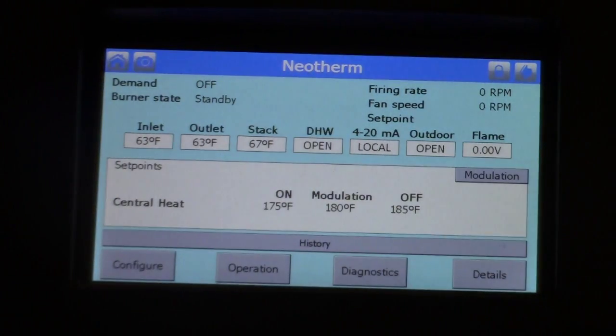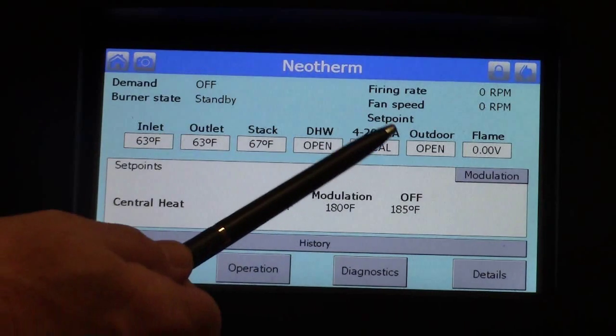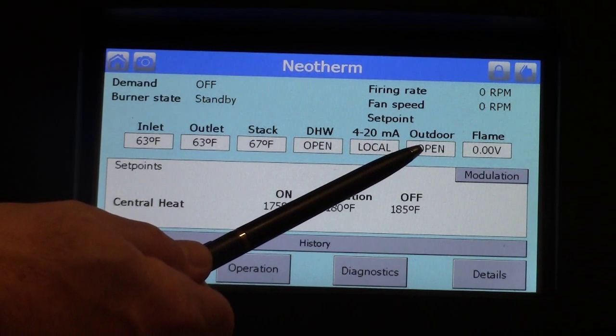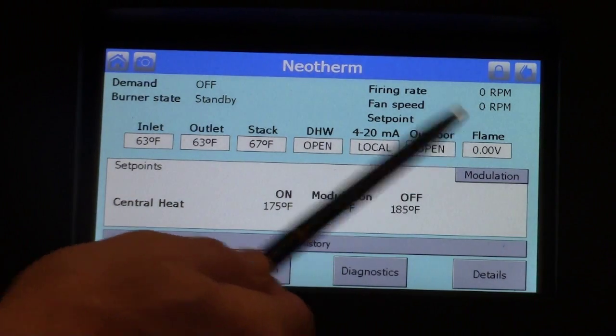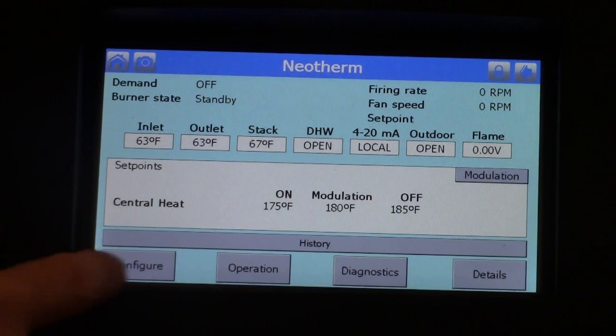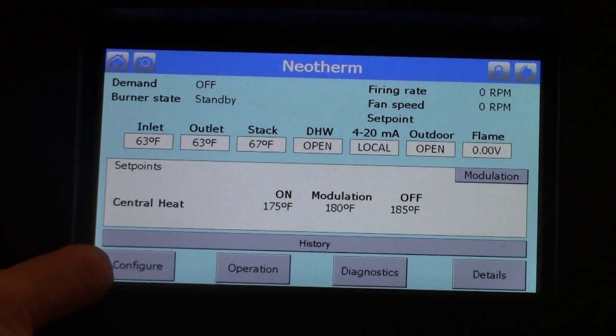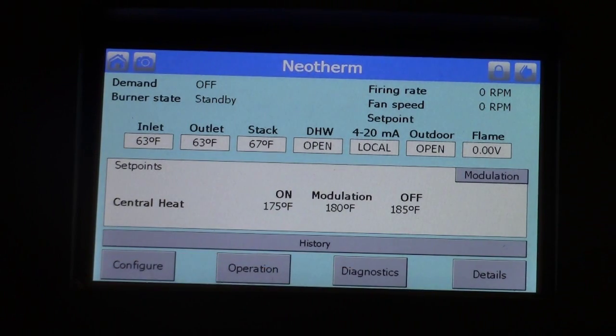We also have the outdoor temperature. We strongly recommend you use outdoor reset and the outdoor sensor that ships loose with this boiler. Once you land that, it gives us the outdoor temperature reading. Then we have the flame signal — while the boiler is running, we can look at what the flame signal is. Down on the bottom we have more information such as configure, operation, diagnostics, and details. We're going to go through a couple of those.